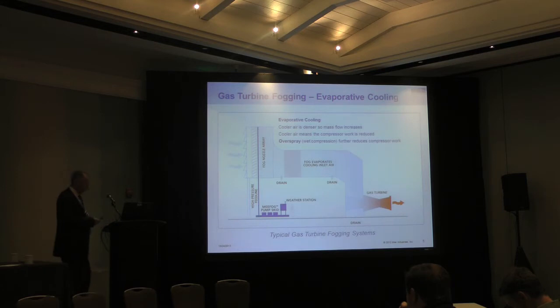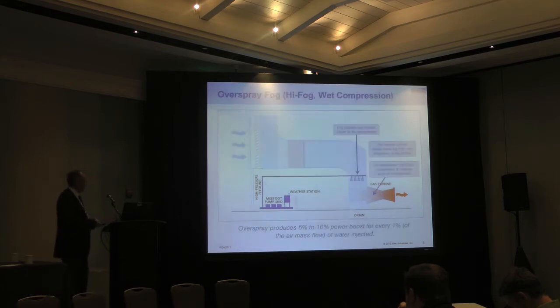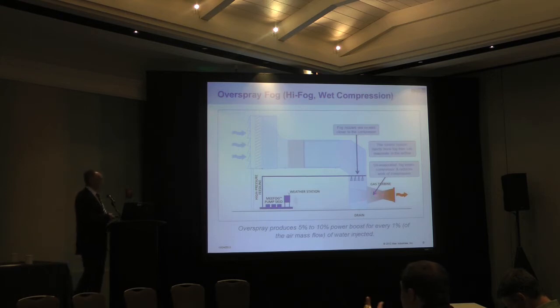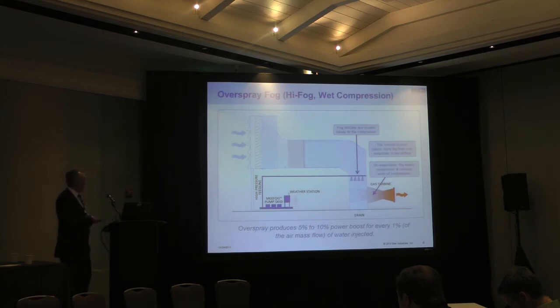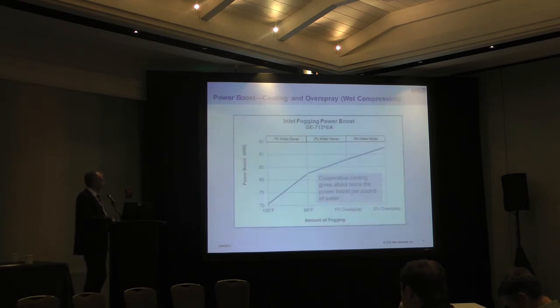But for overspray fogging, we'll actually typically do a slightly different installation. We'll put the nozzles very close to the compressor. Now, this might be evaporative cooling and overspray. In fact, with nozzles located here, there will be some evaporative cooling of the air before it enters the compressor. But most of the droplets will fail to evaporate and will go inside the compressor. So the benefit there is that the droplets evaporate inside the compressor, lower the temperature in each compressor stage, and that reduces the amount of work that the compressor is consuming. So you get a pretty good power boost. Overspray produces about 5 to 10% for every 1% of the air mass flow of water injected. So those are the 2 simple applications of inlet fogging.